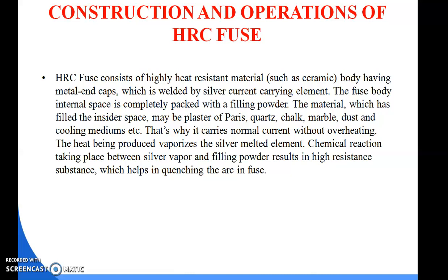The material which fills the inside space may be plaster of Paris, quartz, chalk, marble dust, and a cooling medium, etc. That is why it carries a normal current without overheating. The heat being produced vaporizes the silver melting element. A chemical reaction takes place between the silver vapor and the filling powder, resulting in a high-resistance substance which helps in quenching the arc in the fuse.